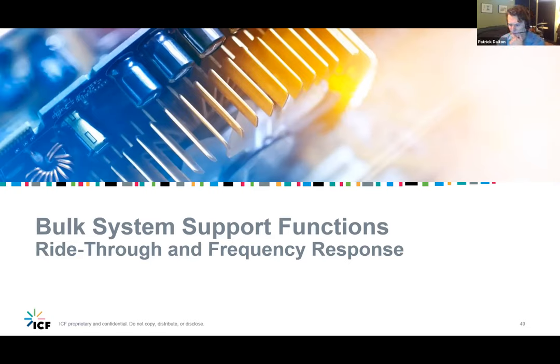So a good question. And then last question I'm seeing here is, can the inverter have both volt var and volt watt function at the same time? In other words, when the inverter has volt watt control in place, is the volt var active? Yes, it's possible to have, let me just make sure. I sometimes see volt watt var and volt watt as the same, but we're talking about one reactive power function and one active power function. So volt var and volt watt, those can be stacked on top of each other.